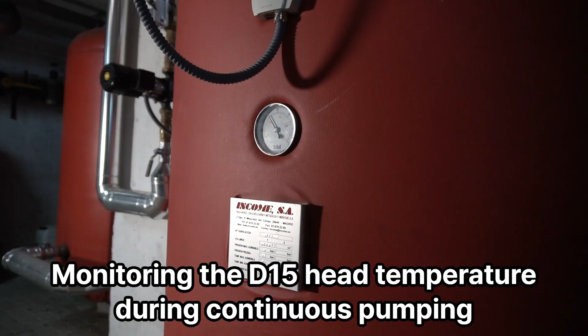Monitoring the D15 head temperature during continuous pumping is therefore paramount. Regular checks, possibly using built-in sensors or external temperature probes, can help identify any unusual temperature increases. Any deviation from the normal operating temperature range should be investigated promptly.